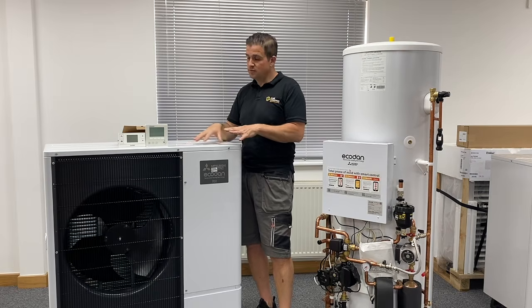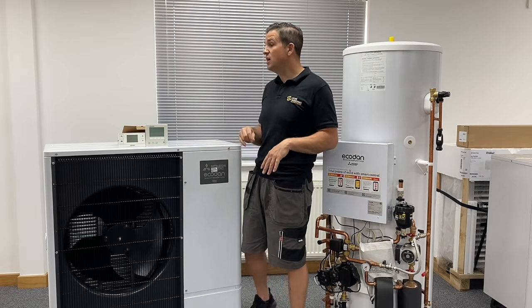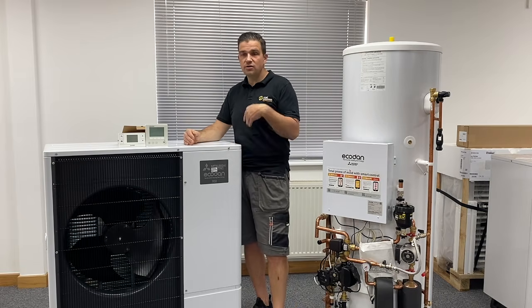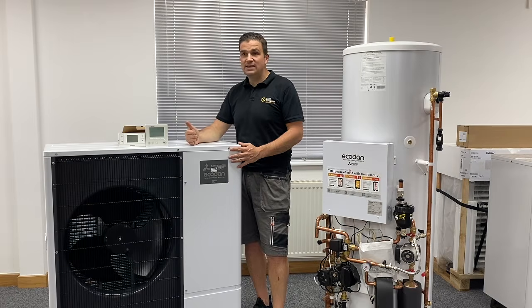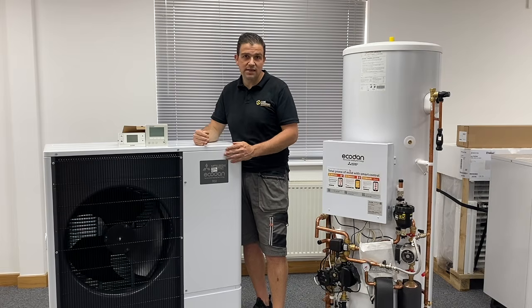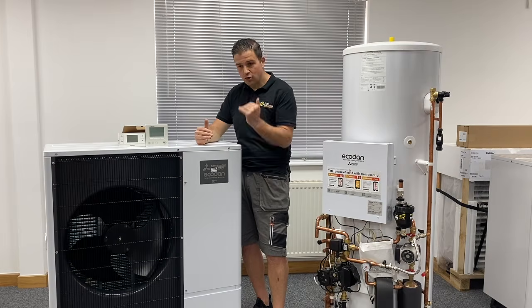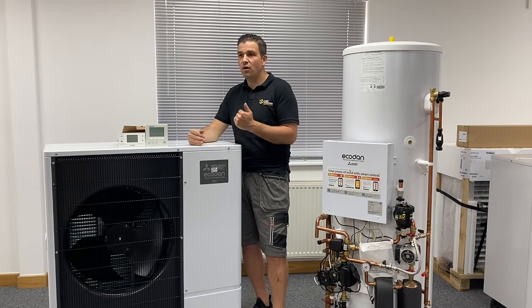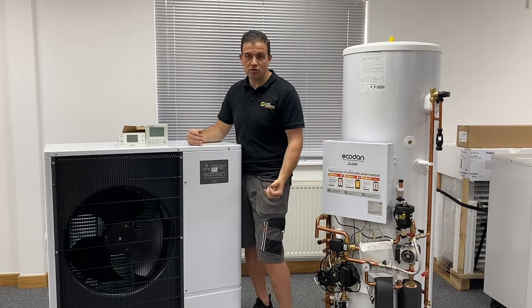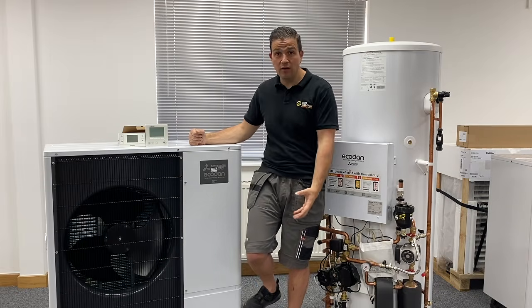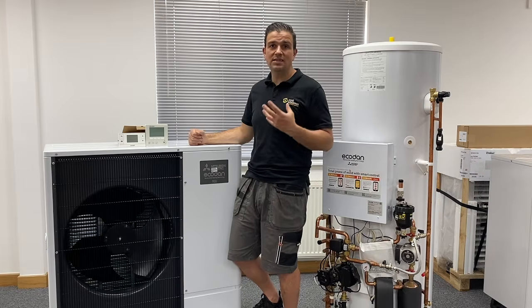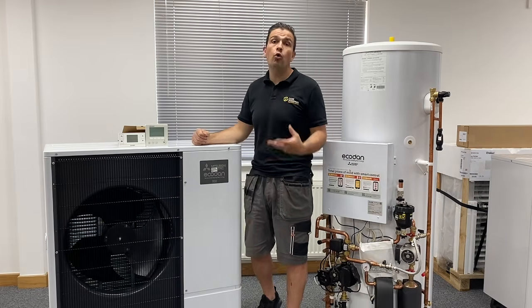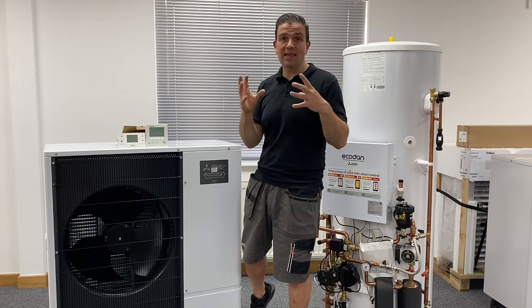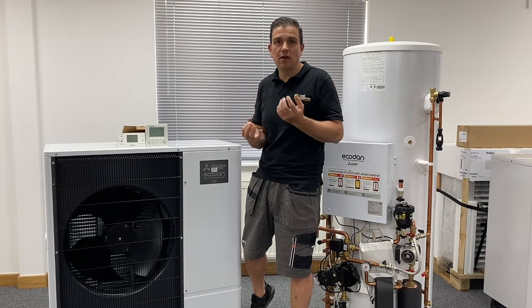Some heat pumps, I'm not talking about Mitsubishi, but some other manufacturers, you might get, say, a -2 or a -3 or a 0 degrees. And it might say it's an 8 kilowatt unit, but actually at that temperature, providing 50-degree heat flow temperature for a radiator, the performance level actually might drop off slightly. So where it was an 8 kilowatt, it might only be able to provide a 6.5 or 7 kilowatt heat output. Therefore, it's really struggling to maintain any heat in the house. It's working very hard, and then you're starting to see that it's going to be expensive to run, or you're not going to get the produced heat that you require, and start feeling slightly chilly in your home.